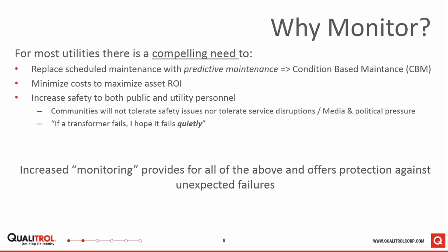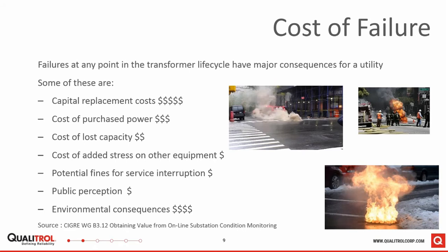A key thing to take note of here is that monitoring won't stop a transformer from failing. What it will do is help inform you when there's a risk of failing, or if the transformer is showing excessive aging. And it will allow you then to take some action to prevent that failure or to manage the aging of the transformer. Okay, so monitoring can help me to manage my assets, potentially save via condition-based maintenance, and maybe even to save lives in an extreme circumstance.